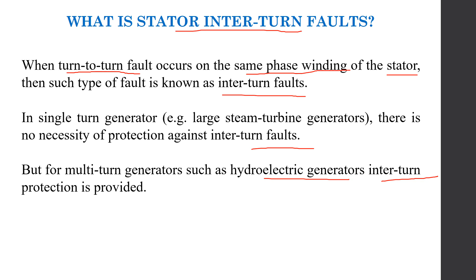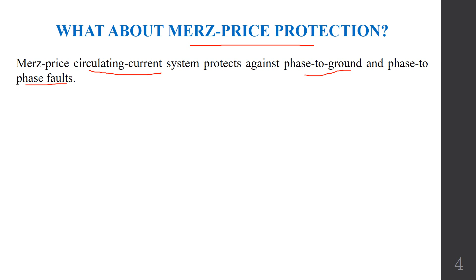So, what about the Merz price protection scheme applied in case of generator? The Merz price protection scheme applied in case of generator protects the generator against phase to ground and phase to phase faults. The Merz price protection scheme is based on circulating current principle. That is, the sum of current entering the circuit and leaving the circuit must be equal to 0. And if that sum of current is not equal to 0, that means a fault is occurring in the circuit. And therefore, in that case, the relay operates.